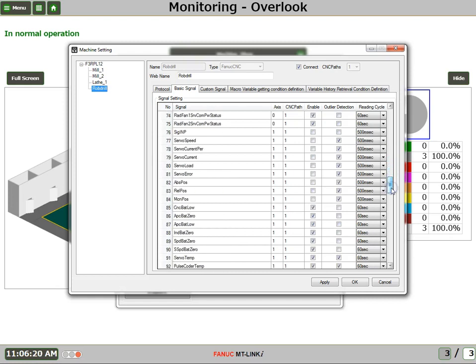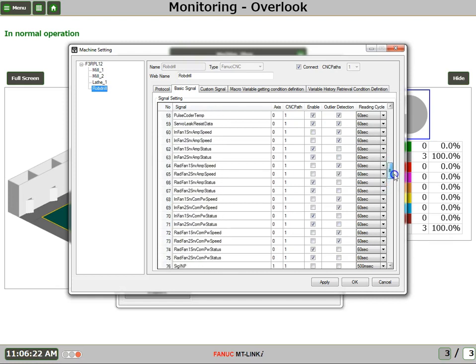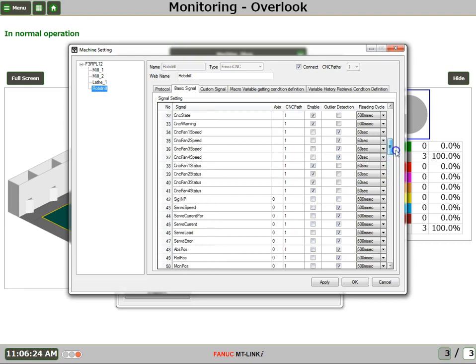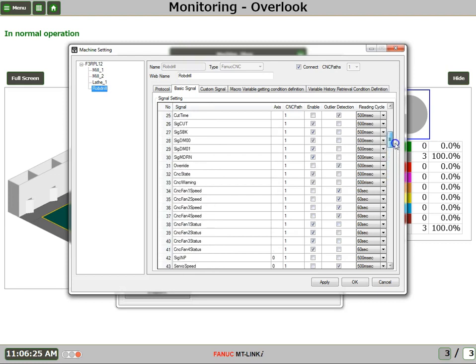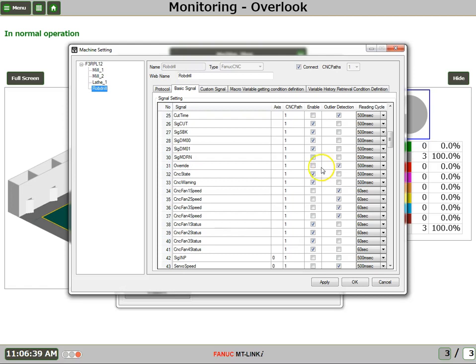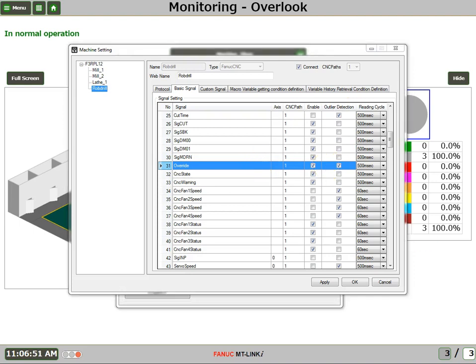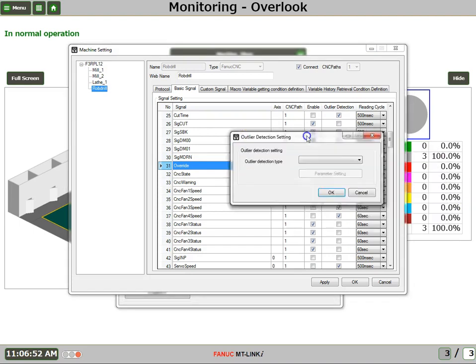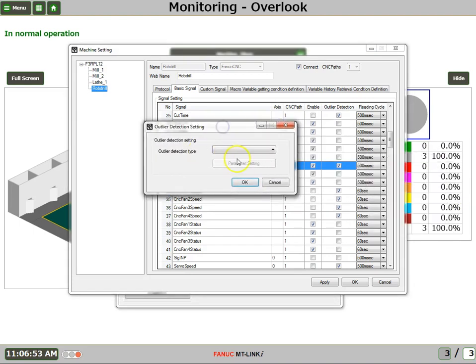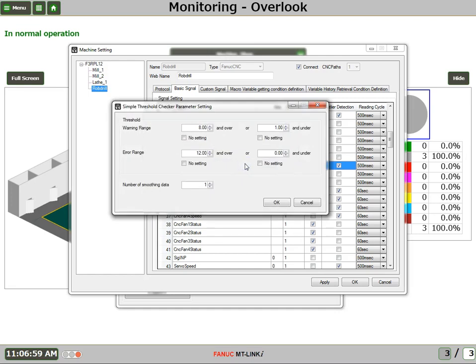However, if there is something that we would wish to change, we can easily do that. For example, let's take a look at the feed rate override. Now this is one signal that's not default enabled. This is partly because each machine could be slightly different in how the override signals are controlled. So first thing we're going to do is say yes. We want to monitor the feed rate override, and we're going to use an outlier detection. What this means is this is thresholds. So we're going to set it up so that there's a simple threshold checker, and we'll open up the parameter setting.